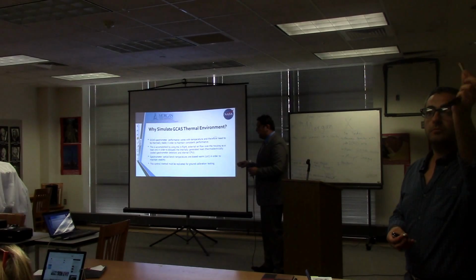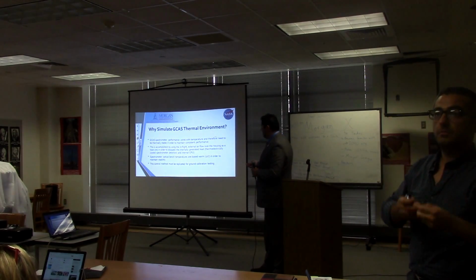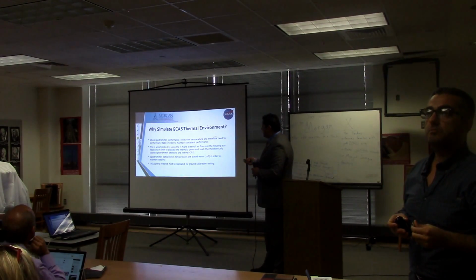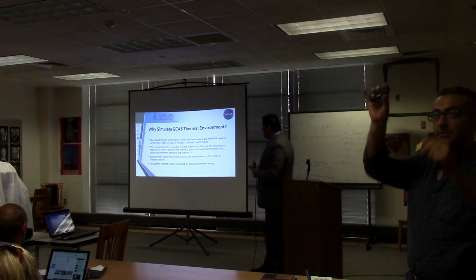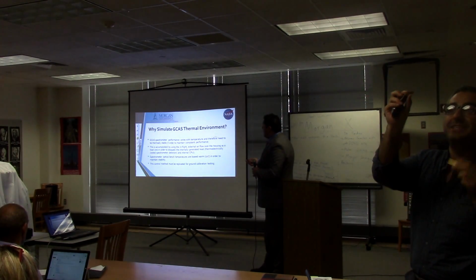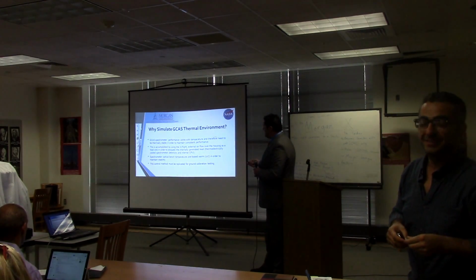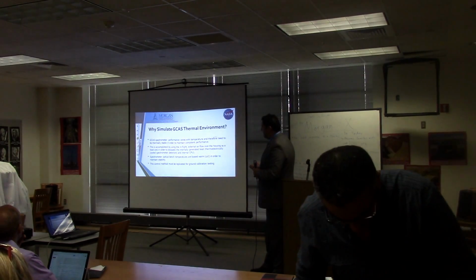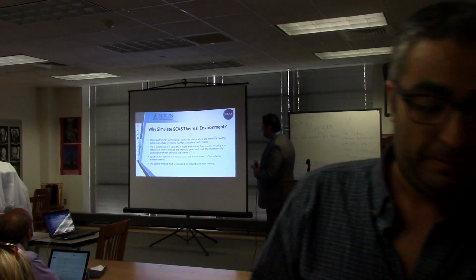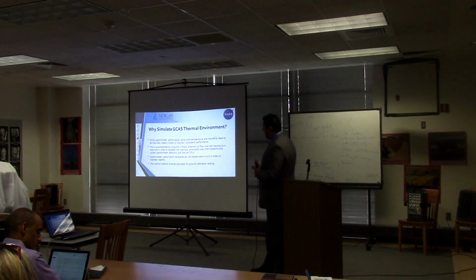Why simulate the thermal environment? Like I said, we need that to make sure that we will have a consistent performance. We want to keep it at 22 degrees centigrade. In flight we accomplish that by using cold external air, and in the lab we need to regenerate that to be able to set our systems.